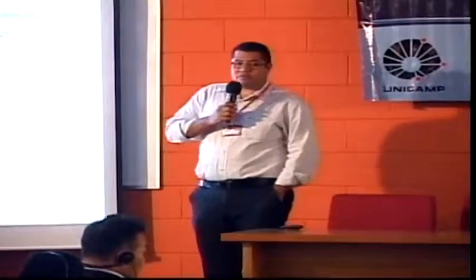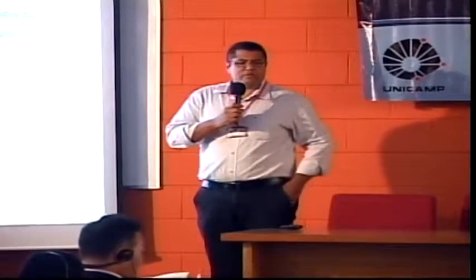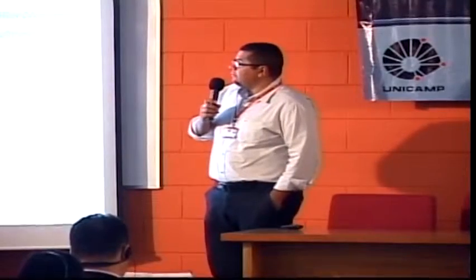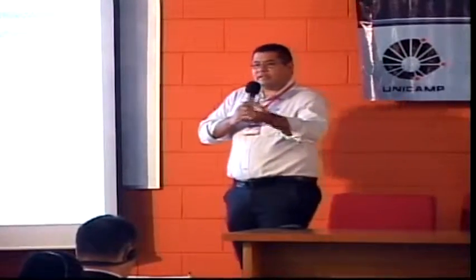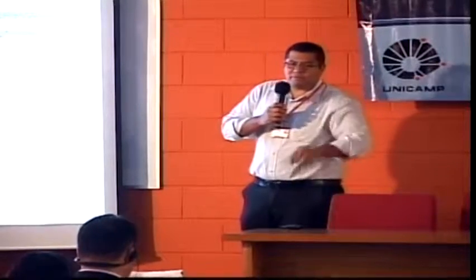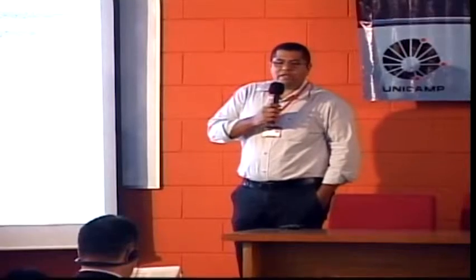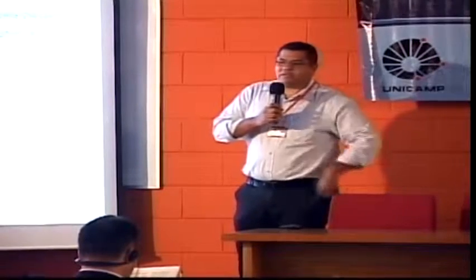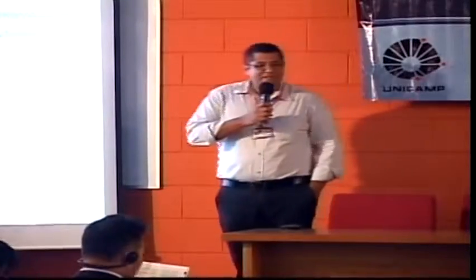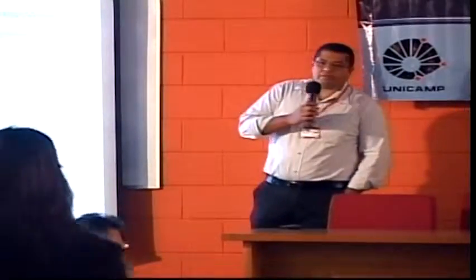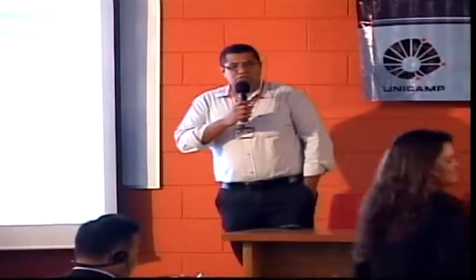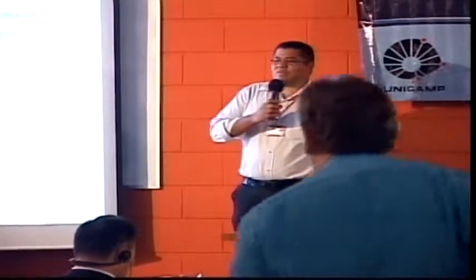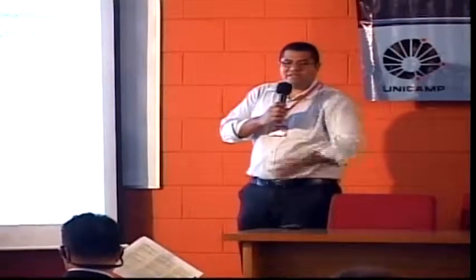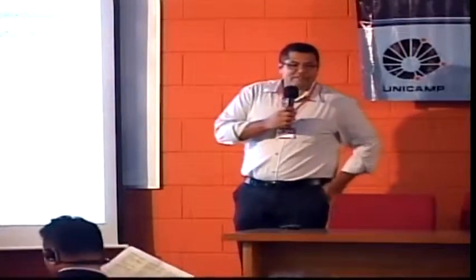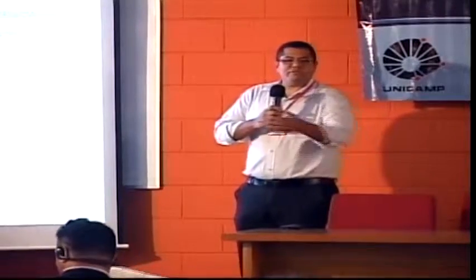The objective here is to try to do some energization studies of the north-south link using the modeling of the generator. The idea is to see the impacts on the generator. You saw several works where the generator was not represented. It's an ideal source of voltage, with some reactance. Here we consider the detailed model for the generator of the Belo Monte plant.